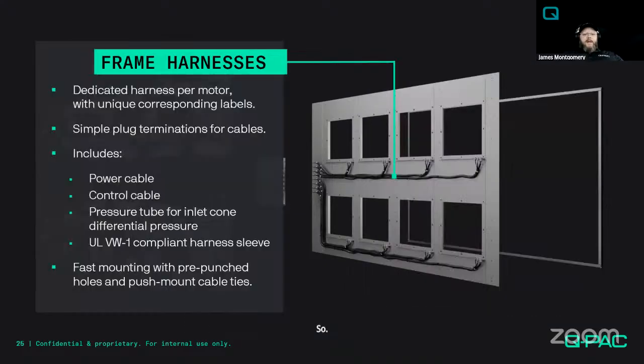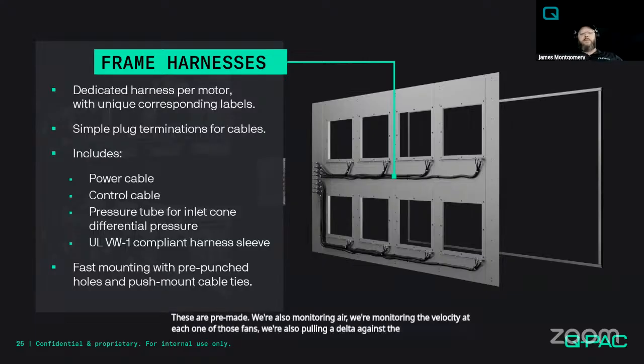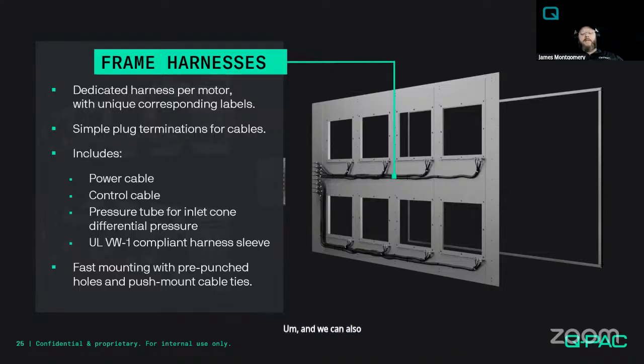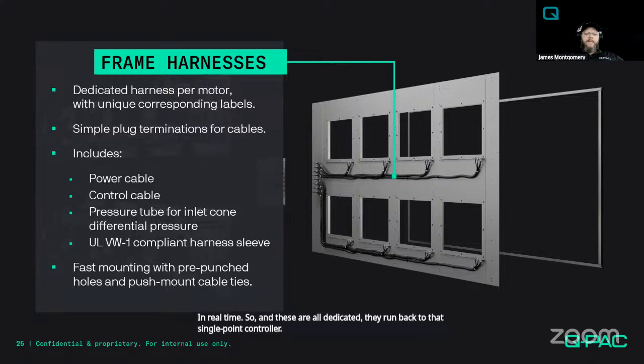So harnesses, kind of already talked about that. So power cable, control cable, there's also a pressure tube there. And these are UL VW1 compliant harness sleeves. And so the point being, these are pre-made. We're also monitoring air. We're monitoring the velocity at each one of those fans. We're also pulling a delta against the wall so we can give you a local interpretation of CFM. And we can also monitor the effects of the system and what's happening with these fans in real time. So, and these are all dedicated. They run back to that single point controller. And they're very fast to mount.